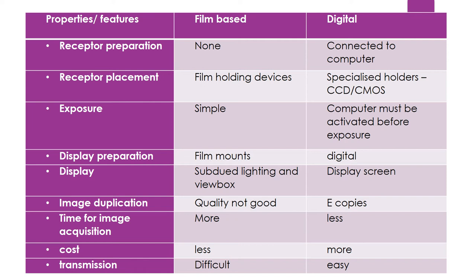A more detailed comparison: for receptor preparation, films need nothing while digital setups require switching on the computer, opening software, and keeping it ready. For receptor placement, film holding devices are used, and for digital sensors specialized holders exist; PSP can still use the same film holding device since it is similar in size to film. For exposure, in both cases the film or sensor is placed inside the oral cavity and the x-ray machine is set; in a digital setting, the computer must be activated before exposure or no image will be captured.